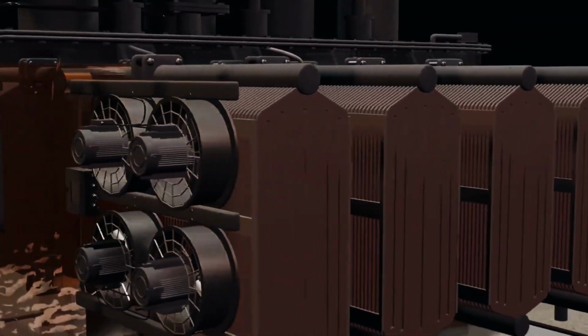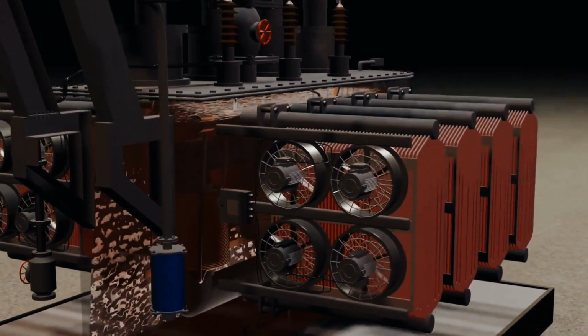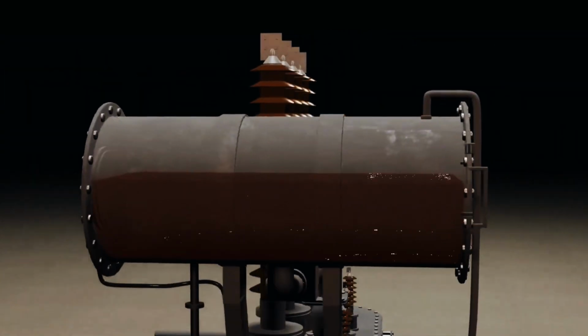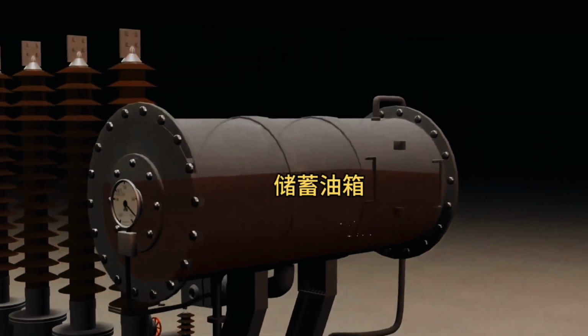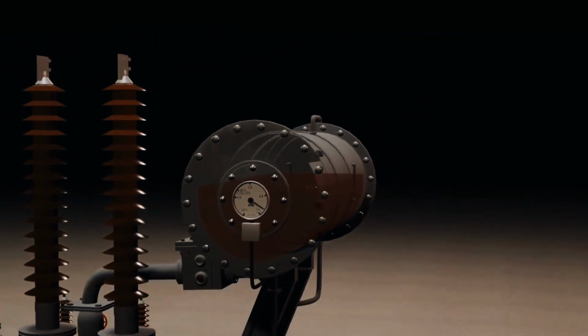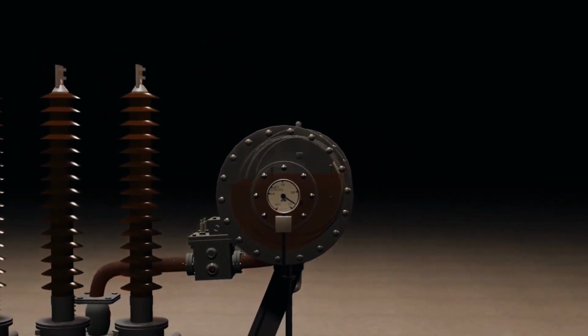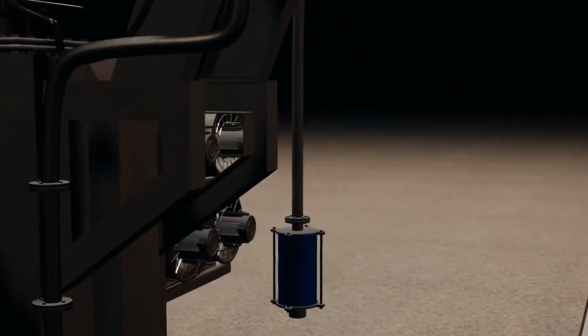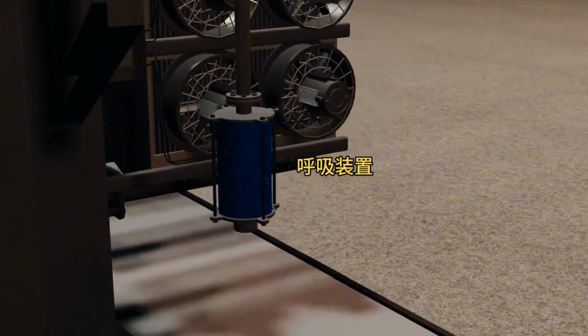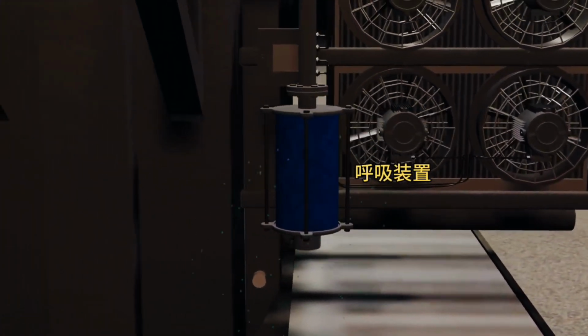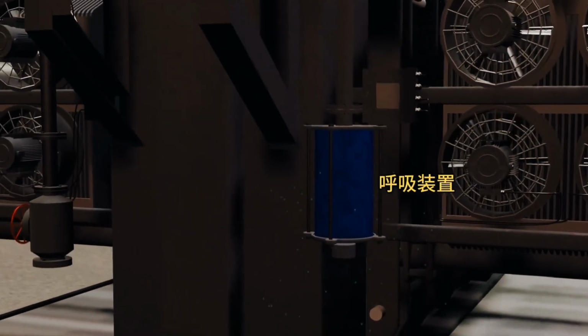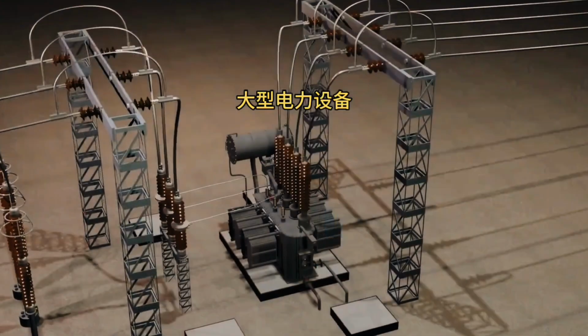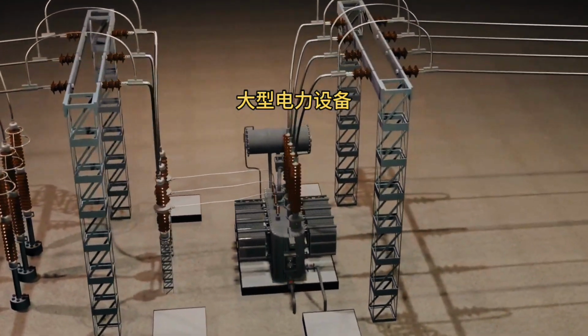Cooling fans are installed on large transformers for cooling, and this on top of the transformer is the auxiliary oil tank, functioning similarly to a car's auxiliary water tank. When the oil temperature rises, it expands and flows to the auxiliary oil tank to relieve pressure, connecting through pipes to the bottom. This is the pressure relief breathing device. Inside, there is filtering material that can filter out air, moisture, and dust impurities, extending the transformer's lifespan. After all, this kind of large power equipment is really expensive.